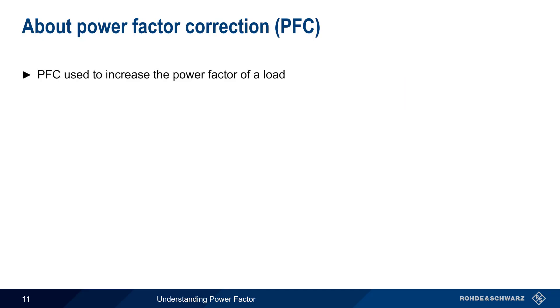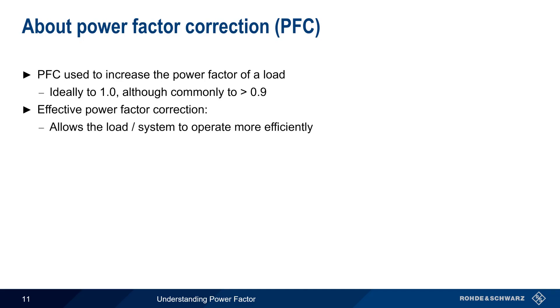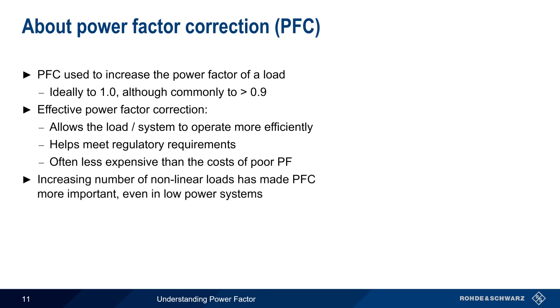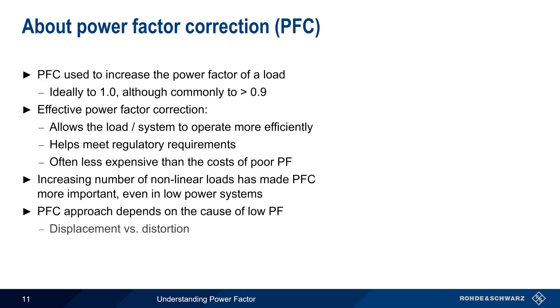Power factor correction refers to methods used to increase the power factor of a load, ideally to 1 or unity, but usually to at least 0.9. Effective power factor correction helps a system run more efficiently, thus saving both utility and equipment costs. In some areas and applications, power factor correction is also required in order to meet standards or regulatory requirements. In many cases, the cost of implementing power factor correction is substantially lower than increased utility or equipment costs. Since the number of non-linear loads has been steadily increasing, the importance of power factor correction has also been increasing, and this is true even for lower power, non-industrial systems. The approach used in power factor correction depends on the cause of reduced power factor — that is, whether low power factor is due to displacement or distortion.